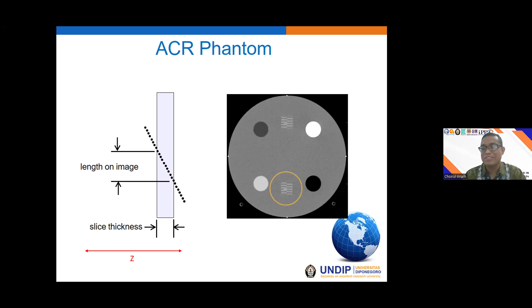So the ACR Phantom is designed for easier use by only counting the objects. To measure the slice thickness, we do not use the caliper, the electric caliper, but instead only count these objects. So for the manual one, the ACR Phantom is easier compared to the CATPHAN or APM. But for the automatic one, it is rather difficult to develop an algorithm to tackle this issue.